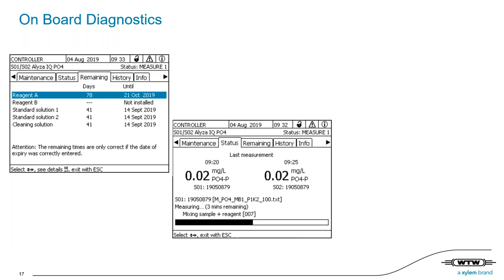Okay, if the analyzer is set to measure at an interval of 20 minutes, can the reagents last for 1 year? Yeah. So this is what I mentioned. The lifetime of the reagents at you as a customer is 18 months. So if you have a 20 minutes interval, it lasts 1 year.